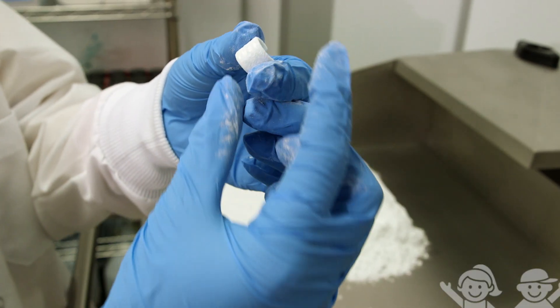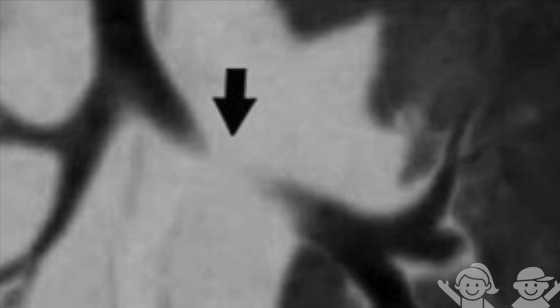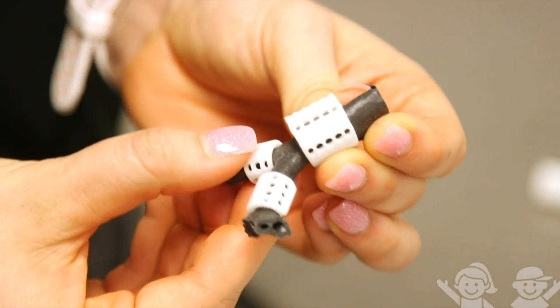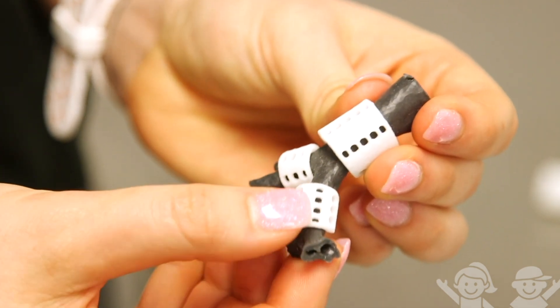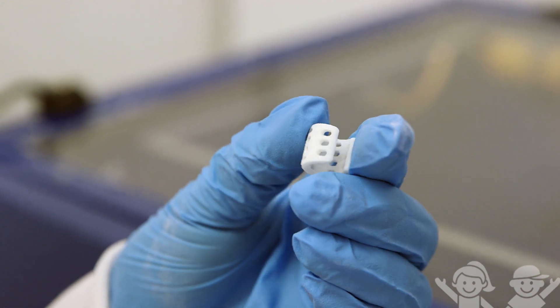Fortunately, one of the folks who developed a novel treatment using 3D printed material to support and prevent the floppiness from occurring is actually here at Georgia Tech now. The first thing we do is get the CT scan from the surgeons, because we use that image data to actually build a digital model of the patient. From that model we get the parameters — the length of the collapsed segment, the diameter — and we use that to design the devices. In this case, there were three devices implanted.